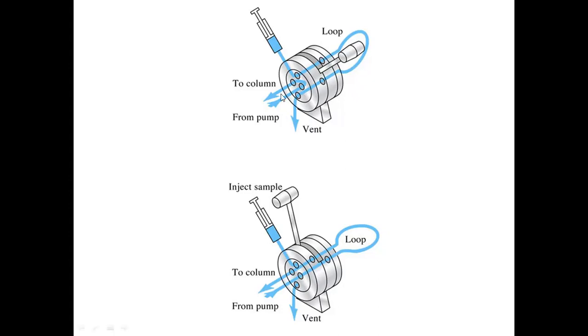after the injection is over, if you bring the loop towards the injection mode, the introduced sample is going to travel towards this loop and it is going to be combined towards the chromatographic column. See here, arrow mark. So from the pump the mobile phase is coming. Mobile phase will be carrying the solute which has been introduced, and it will be combining towards the chromatographic column. So therefore this valve loop injector will be playing an important role.